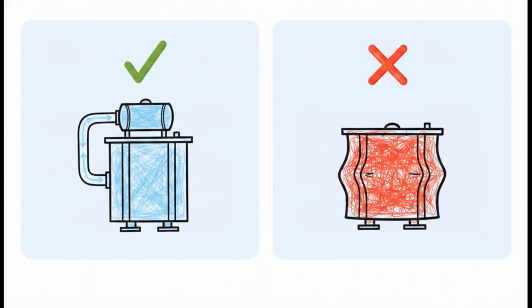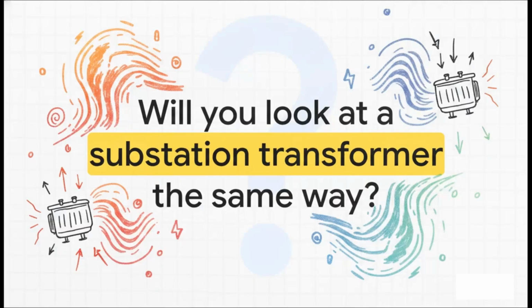To really appreciate this elegant engineering, we have to look at a hypothetical. What if we just sealed the transformer completely tight without that top tank? Well, in a system with a conservator tank, the oil expands safely, pressure remains completely stable, and the grid runs smoothly. But without it, the story is very different. The heated oil expands, but it has literally nowhere to go. Internal pressure gauges would rapidly spike right into the red zone, and the immense hydraulic pressure would begin to warp and deform the heavy steel walls of the main tank, triggering every warning indicator in the substation. It is a pretty stark reminder of the sheer physical forces at play just steps away from our sidewalks and roads.